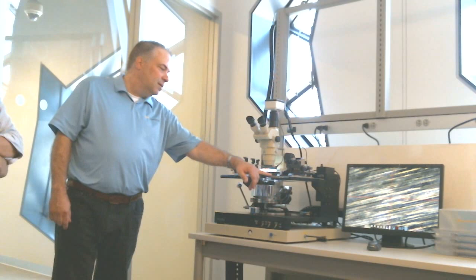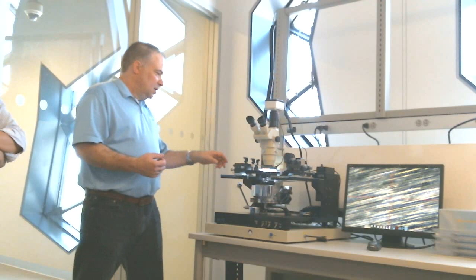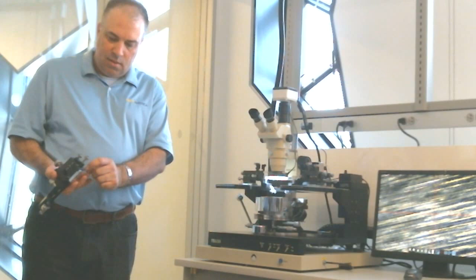If we go down a little bit more, you have the probe platen here, so this is where your positioners are going to sit. Basically the positioner, in this case, has a magnetic base to it. You rotate the lever in one direction, it'll align the magnets, giving a very strong magnetic force. Throw the lever the other way, it'll turn off the magnets, quote unquote, but there'll still be a little bit of residual magnetism there, it won't completely go away. So it does take a little bit of force to pull it off and move it around as you need to.